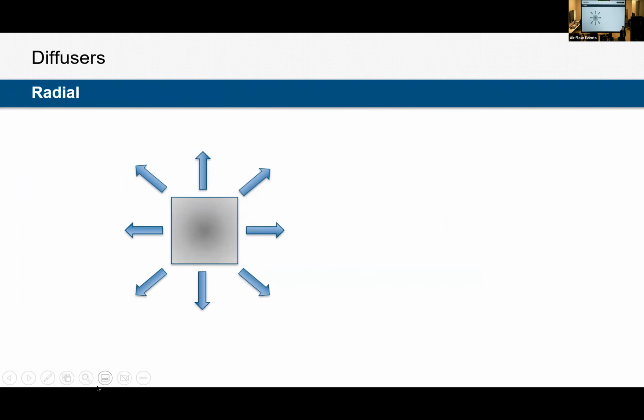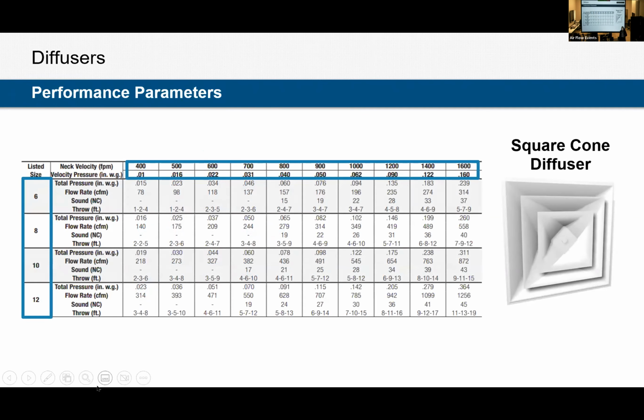If we just go back to the previous slide, I do notice many engineers selecting their neck sizes too large, which for design conditions, like I see a lot of 8-inch diffusers at 200 CFM, for example, works great at 200 CFM, but what happens when we turn down and turn the heat on is we get absolutely no mixing. So you're getting 7 feet. Or maybe it's 300 CFM, you're getting 9 feet. So let's cut the airflow in half. We're not even getting to the wall. And then let's add some buoyancy. So it's not a great habit that we're oversizing diffusers.